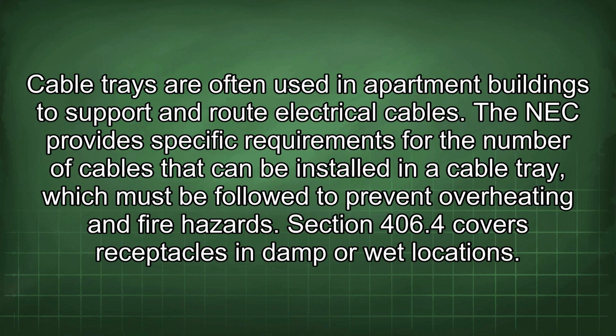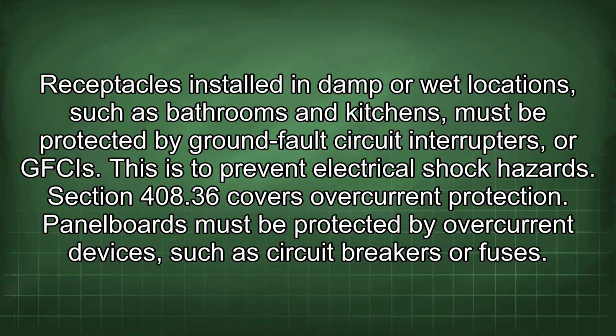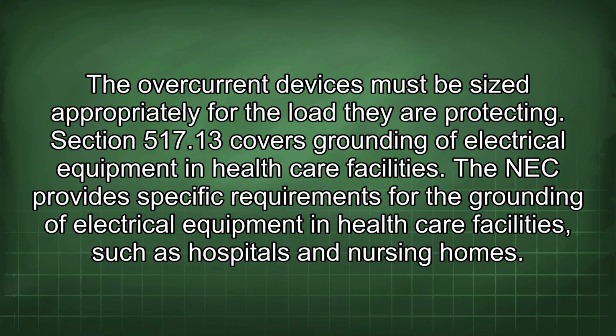Section 406.4 covers receptacles in damp or wet locations. Receptacles installed in damp or wet locations, such as bathrooms and kitchens, must be protected by ground fault circuit interrupters, or GFCIs. This is to prevent electrical shock hazards. Section 408.36 covers overcurrent protection. Panel boards must be protected by overcurrent devices, such as circuit breakers or fuses. The overcurrent devices must be sized appropriately for the load they are protecting.